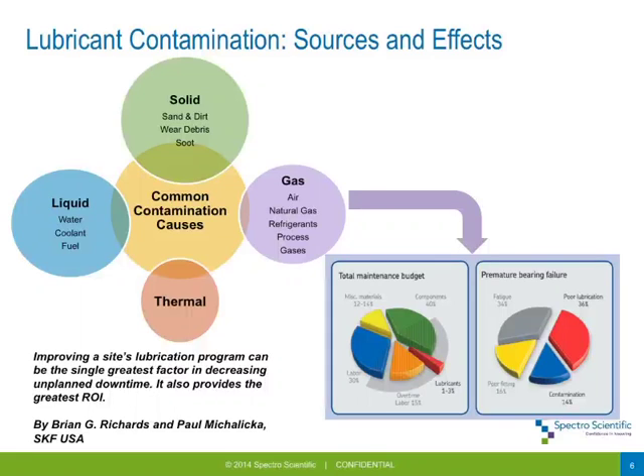It's really important to see that if you tackle lubricant contamination, you can have a direct effect on your bottom line. It is the best way for anybody considering an on-site oil analysis program to start, because you can see real tangible benefits and a return on your investment in the shortest possible time. A study from SKF identified that contamination and poor lubrication account for almost half of premature bearing failures, and that your total maintenance budget is majorly impacted by those premature bearing failures.